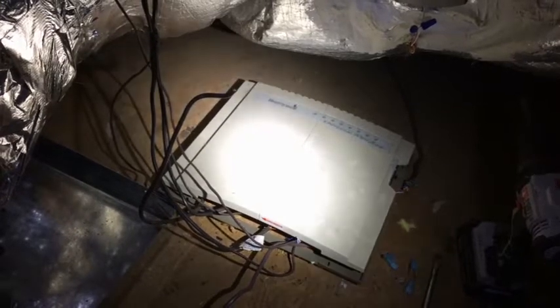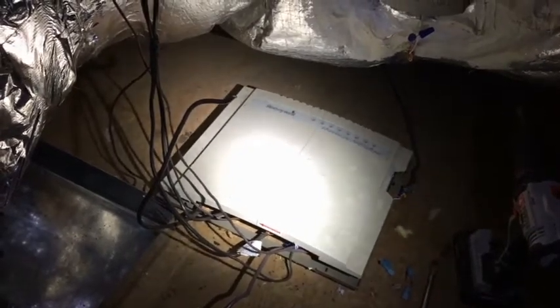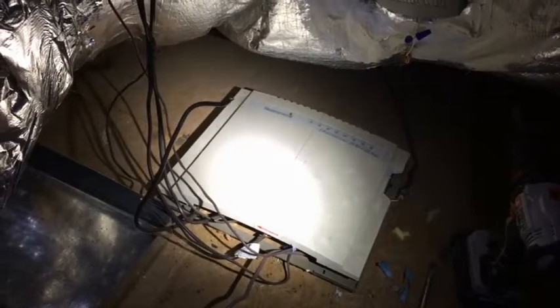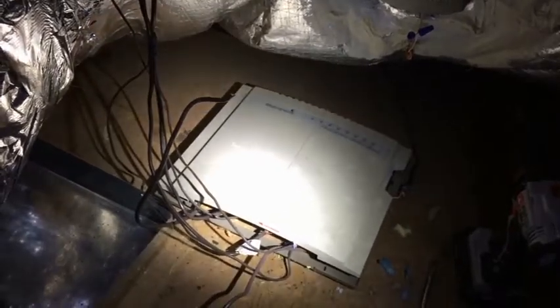The Honeywell FocusPro 5000 on the wall is pretty easy, just reprogram for a B terminal instead of an O, which is the reversing valve. Energizing in cooling is O, and heating is B. So I just need to make sure it's set up. I've got a few wires I need to extend up to the top here, and I had to add this transformer back down here for the zone panel.